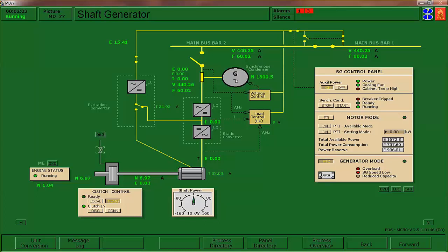The synchronous condenser, you can see it runs at 1800 RPM. That is a synchronous motor that is being used for power factor correction. So in other words, it's just a synchronous motor. It's not driving a load, it's just sitting there spinning. What it does is its excitation is automatically raised or lowered, and by doing that it will create kVAR and shift the power factor, since most ships are about 0.8 power factor, from 0.8 to 1.